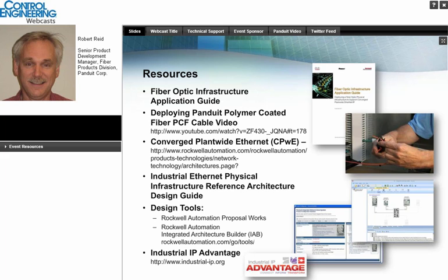Great, thanks. What are the effects on fiber optic cable of kinking and also folding if the cable is too long? I know you showed that slide with the loops and talked about the tighter radius. Yeah, unfortunately, there are fiber manufacturers out there that have produced what they call bend-insensitive fiber. It's a great technology, but it gives a confusing message to users. It's not bend-insensitive mechanically. It is bend-insensitive optically.